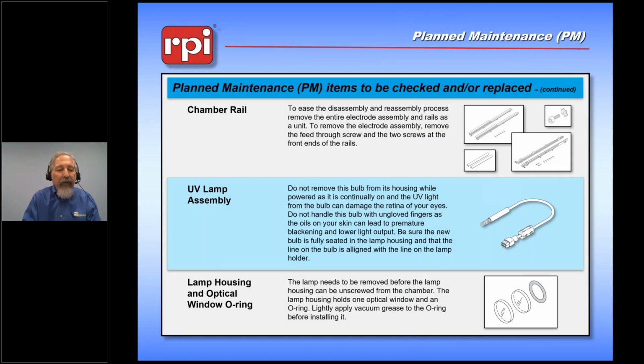Okay, chamber rails. As we said earlier, the chamber rails tend to decay over time with exposure to the peroxide. So every year we want to be sure we put new plasticware into the chamber, and they are included. There is also a UV lamp, as we talked about earlier. Please do not handle the UV lamp without wearing gloves. The oil from your skin can damage the lamp and blacken it. Make sure that you have the correct Allen wrench to remove the original lamp, it's a very small one, and that you get the new lamp in properly seated and that the line on the bulb is aligned with the line on the lamp holder.